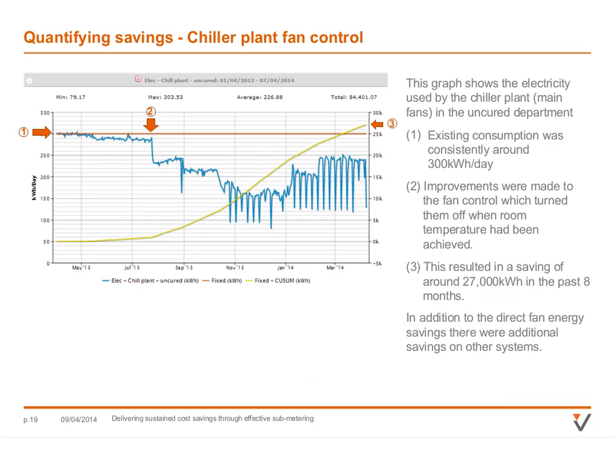When the temperature within the rooms is reached, normal standard refrigeration systems shut the gas down, but the fans continue running. This system senses when the temperature's been reached and shuts the fans down too. The fans then start up once every hour to recirculate the air and make sure the room temperature is correct, shutting down again if not needed. If it is needed, the system starts up and chills the room down again.